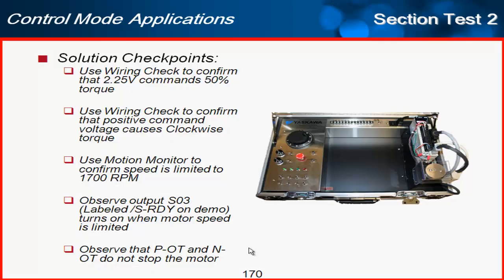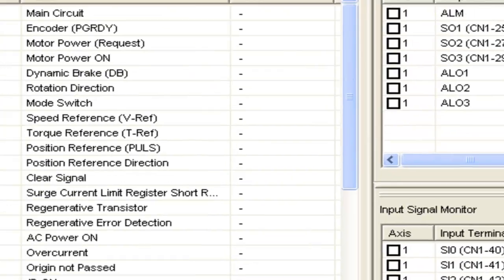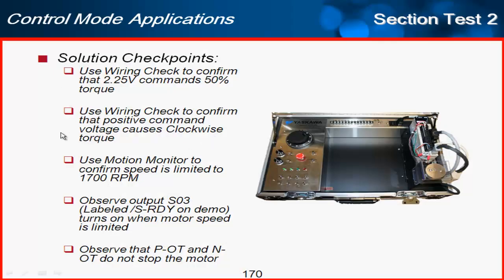Now to test this parameter set on the demo — this is the demo used here at Yaskawa Training, with all inputs and outputs wired and a small motor with a wheel on it. I'll first use the wiring check, which is a good way to confirm your command voltage is correct. Under Monitor, Wiring Check, I'll turn up the torque to 2.25 volts and confirm that produces 50%. There it is — 2.25 volts, 50%. With this positive voltage, I can see the motor is moving clockwise.